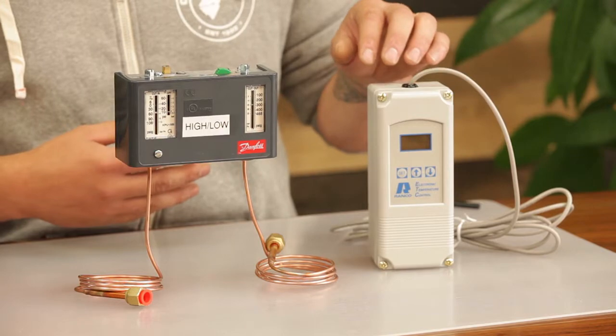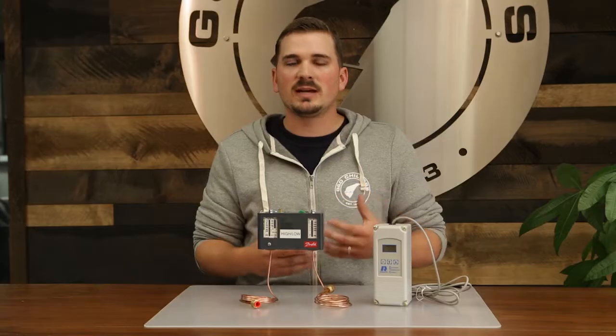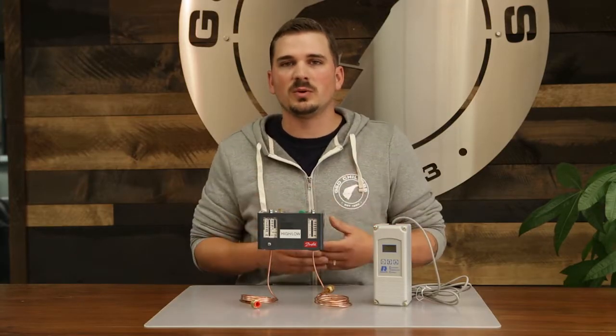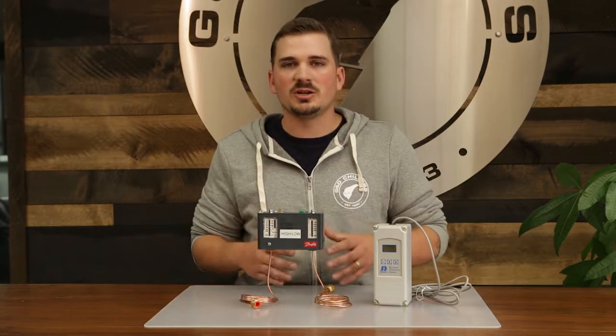Also, this is going to protect against high temp situations. If the glycol ever gets too hot because the compressor is not running, once it reaches the set point, it's going to shut your pump down to prevent any heat being introduced into the system.